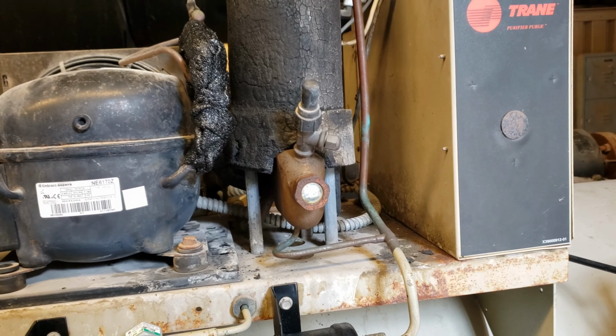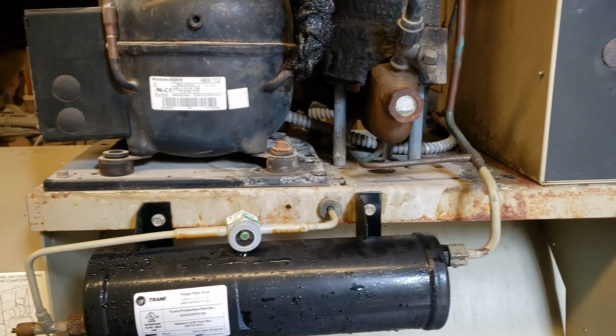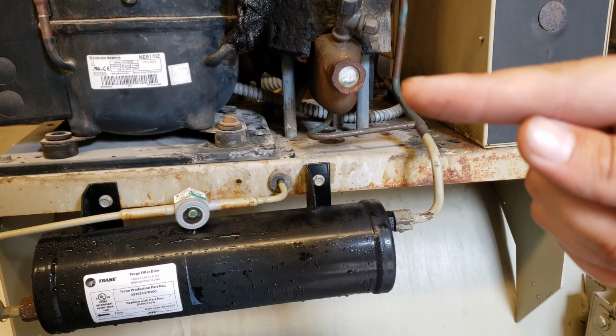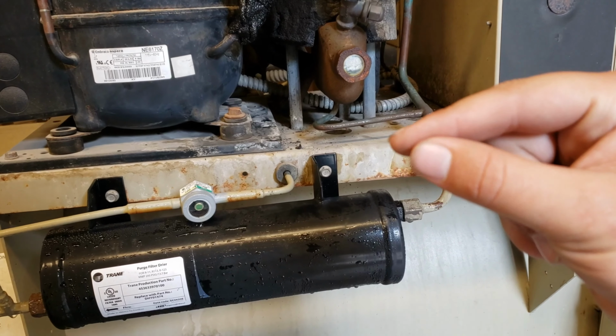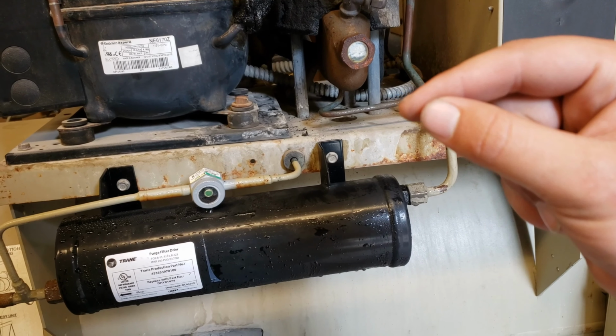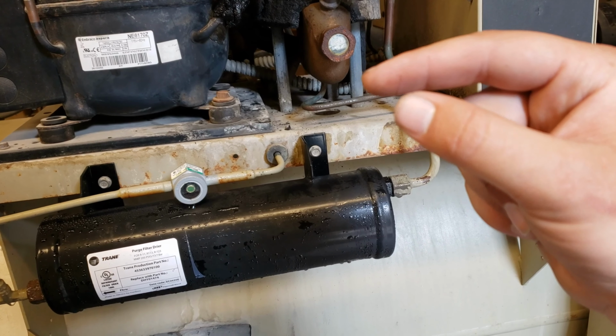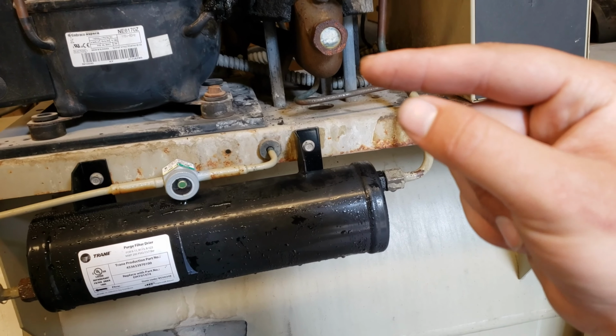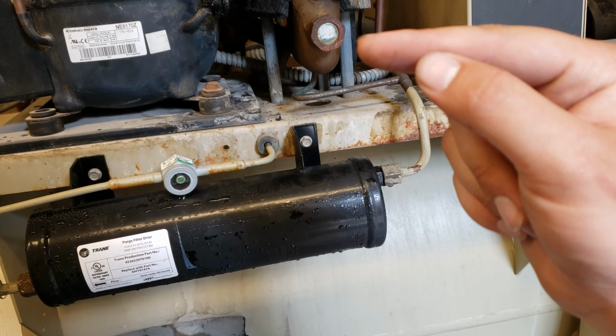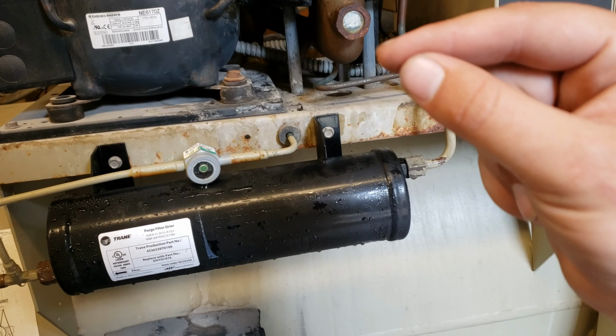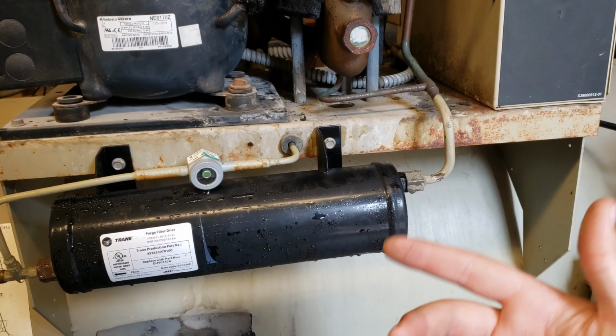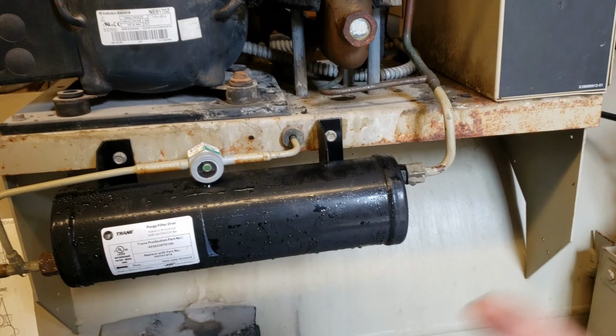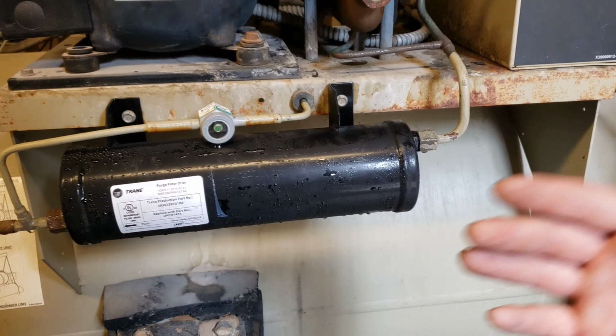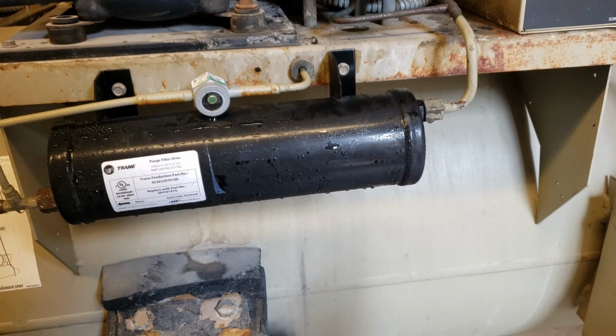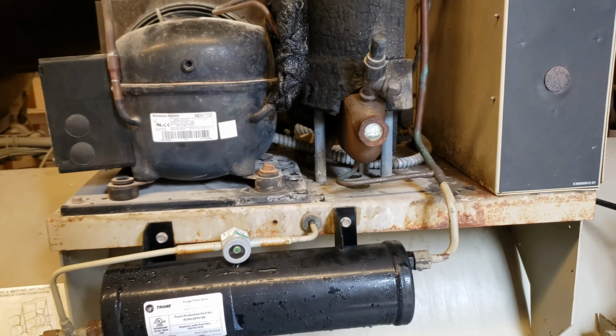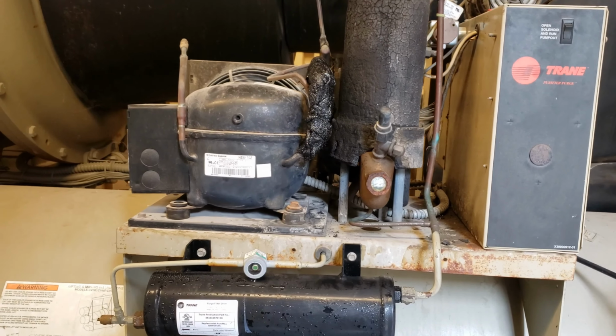to the suction pipe. The problem with that is, you've got the body of the sensor itself, we'll say is this part of my finger, and the very tip of the sensor is the thread, and it's significantly smaller than the main part of the body. Well, the actual sensing element is in the tip of those threads. So what they had was the body was making surface contact, but the tip wasn't. It was just reading air relative to the pipe. And it wasn't very well insulated either to begin with. So what that did is that made it read a good 10, 15, sometimes 20 degrees off from the actual suction pipe temperature. So it never knew that it needed to purge because the algorithm that does that wasn't getting accurate readings.